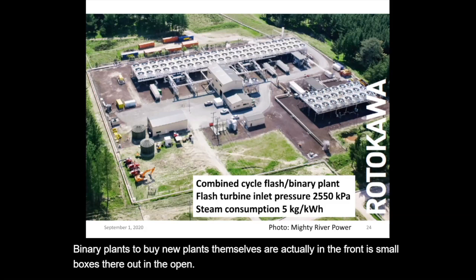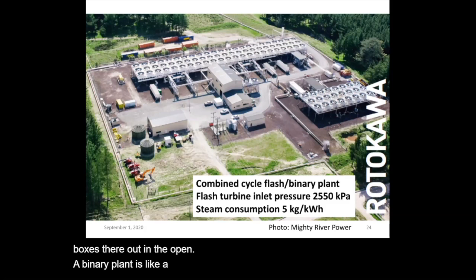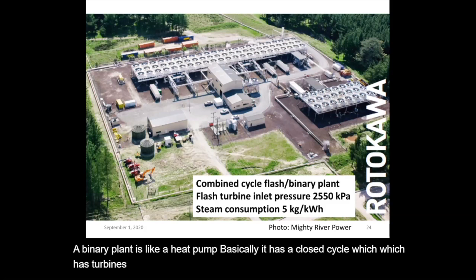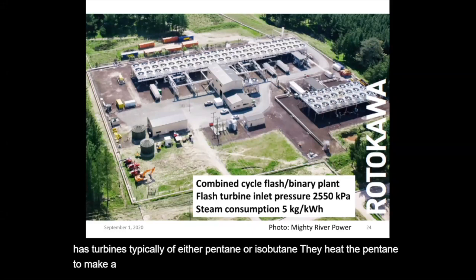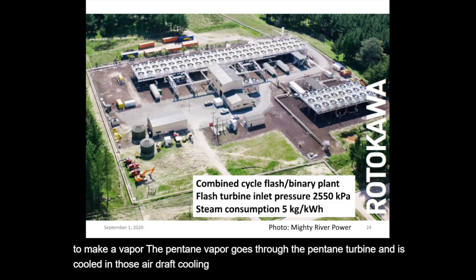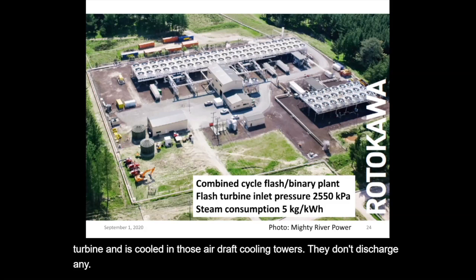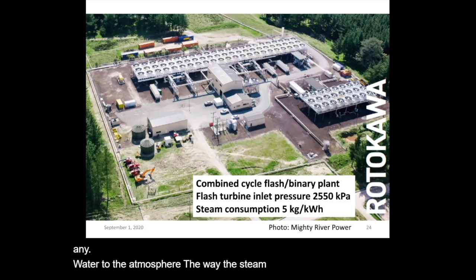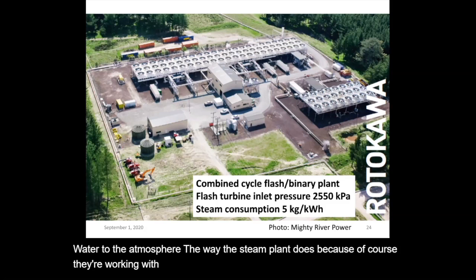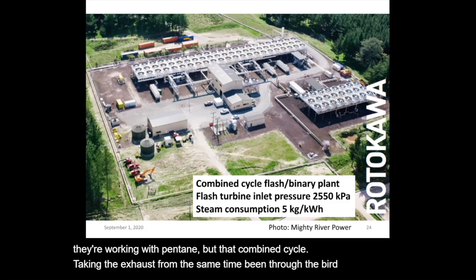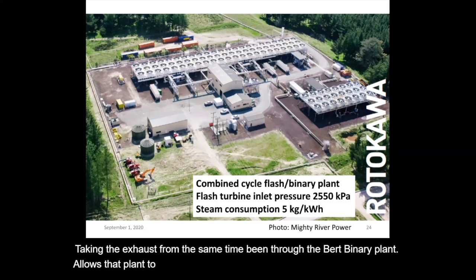A binary plant is like a heat pump, basically. It has a closed cycle, with turbines typically using either pentane or isobutane. They heat the pentane to make a vapor. The pentane vapor goes through the pentane turbine and then is cooled in those air draft cooling towers. They don't discharge any water to the atmosphere the way the steam plant does, because they're working with pentane. That combined cycle, taking the exhaust from the steam turbine through the binary plant, allows that plant to have a very high efficiency.